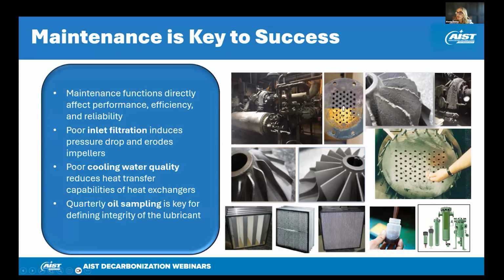And the essence of this performance degradation is an example where we would have a 1,000 horsepower compressor that should deliver about 5,000 CFM of compressed air. When you have this degradation happening, that 1,000 horsepower compressor may only be able to deliver 3,500 CFM or maybe 4,000 CFM. So you see, essentially, you would have to turn on another compressor, use more power to deliver the same amount of flow to your process. So these are some key contributors to optimizing the system with performance and reliability.